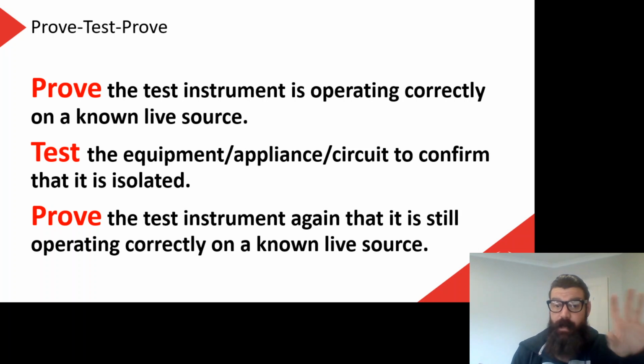our meter again. We go back to the same known live source or a different one. It doesn't matter as long as it's something that we know is live, and we're testing that we're going to get a live voltage there. That proves that my meter is still working. We proved it at the start, but just in case something has gone wrong, I might have connected my meter incorrectly or something and blown a fuse in it. We prove after we've done the test that our meter is still working. That way we know that our test result was valid.